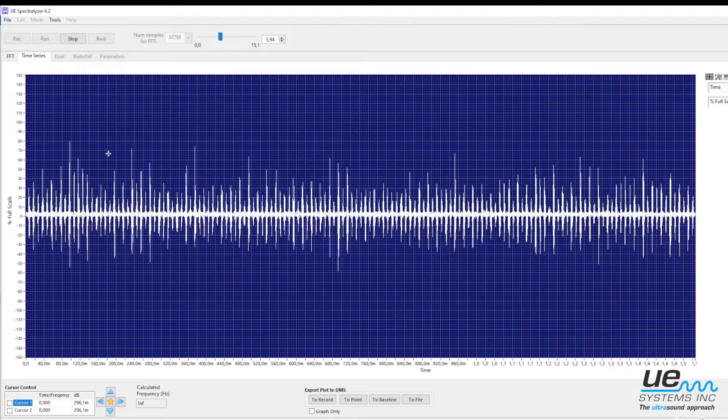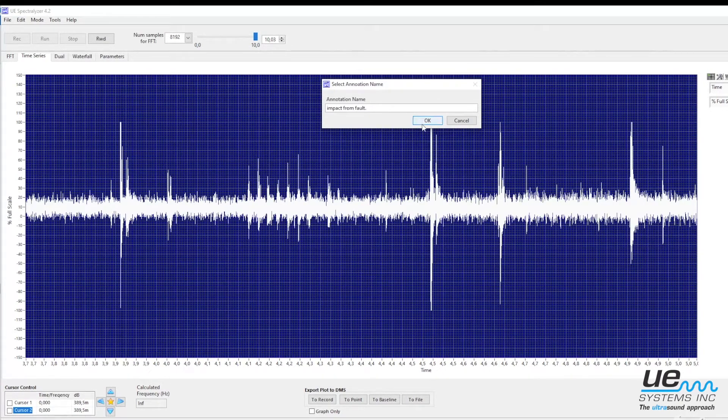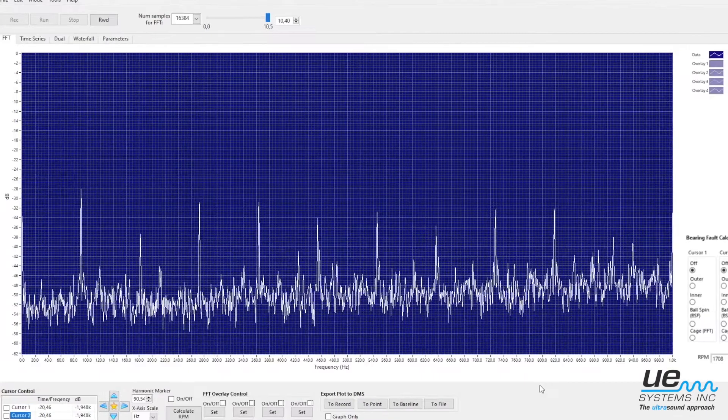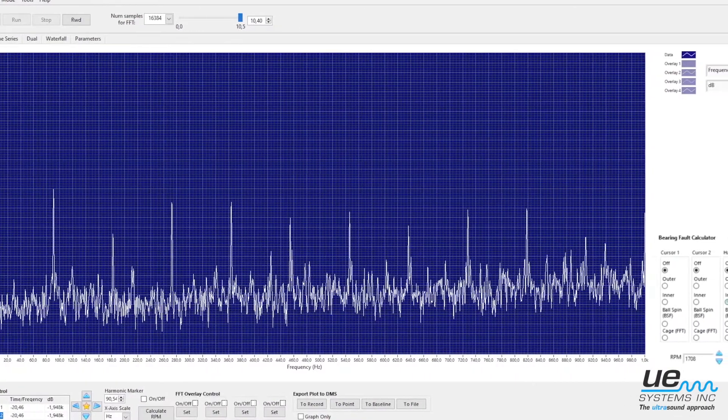It is especially useful to diagnose electrical faults as well as problems with slow speed bearings. The software also features a bearing fault calculator which can estimate the type of fault in a bearing.